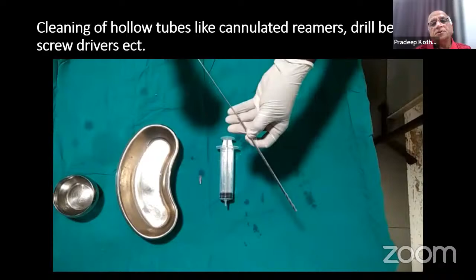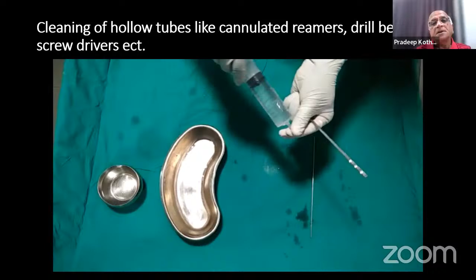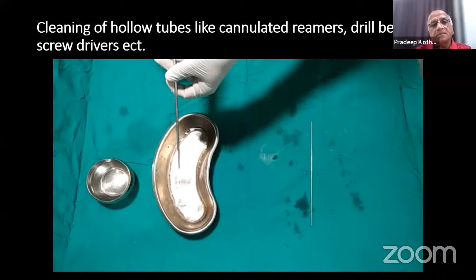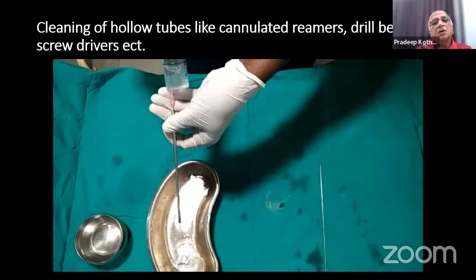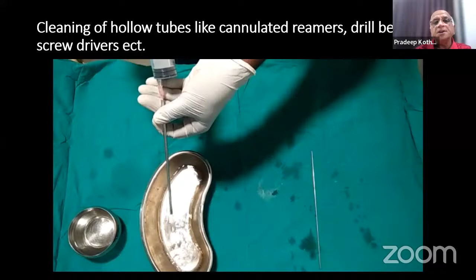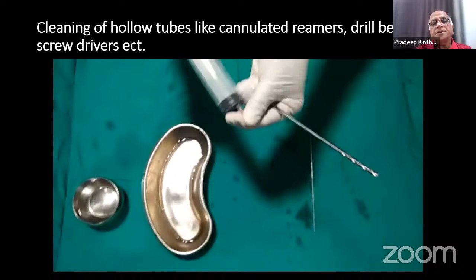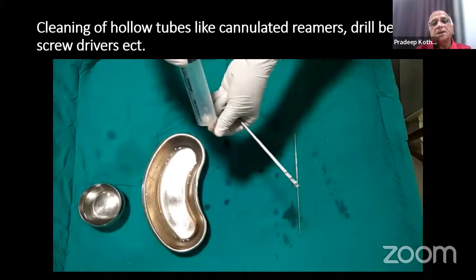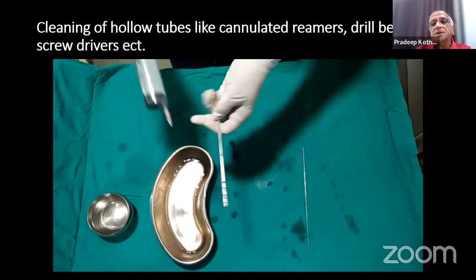This is a step we do. This is the drill. First, you put a guide wire through it, clean it, and take out all the debris. Then take a 10 or 20 cc syringe. Take good tap water and put water through this cannulated instrument. See, the water should come out. Once you rinse with the water, the next step is to take air into that syringe and again put that air through the hollow tube, so that whatever water is inside comes out and it becomes absolutely dry. So this is the way we clean the cannulated instruments.